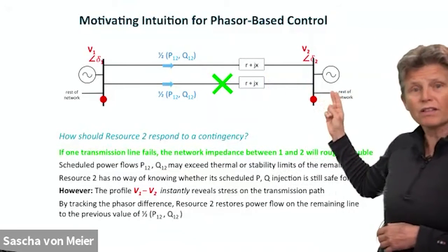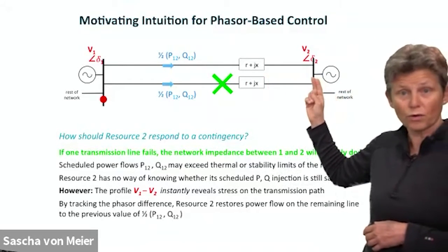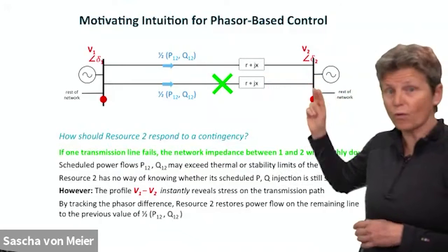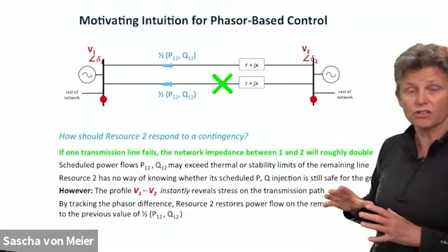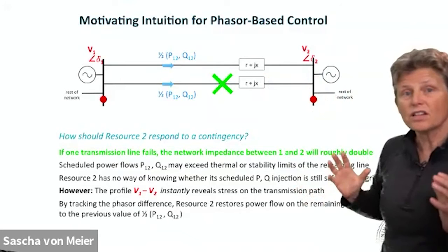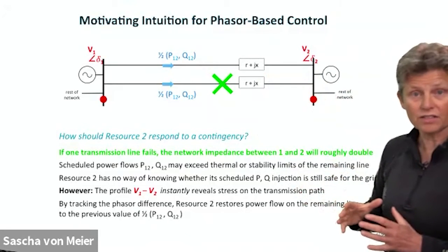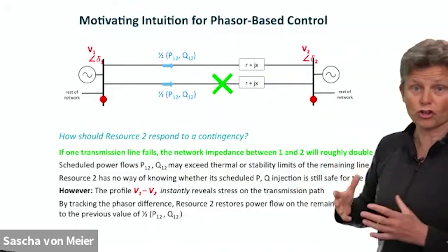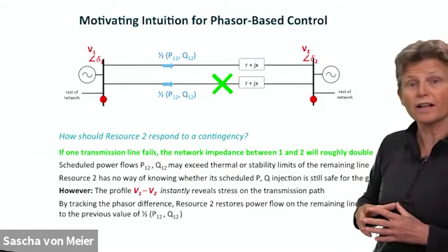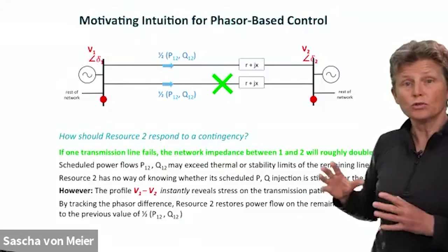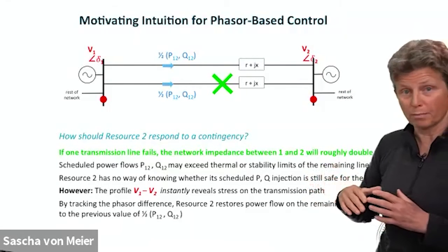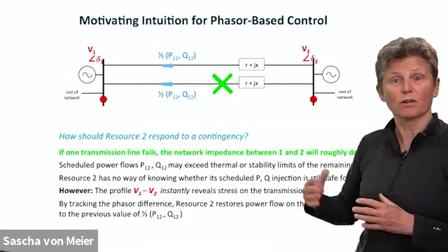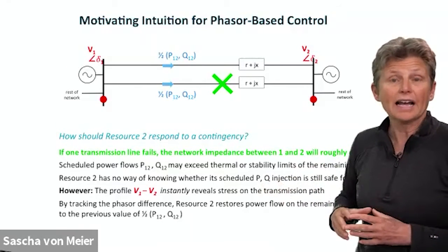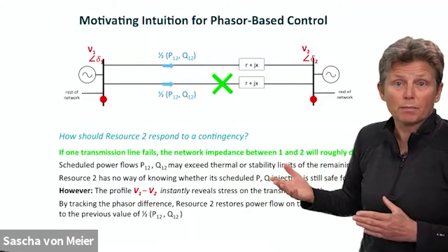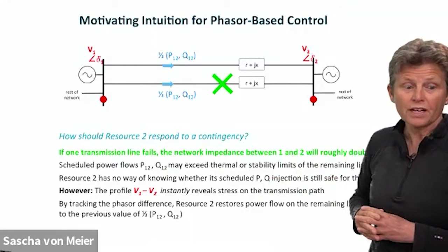By driving this resource back to restore the phasor difference that was there before, regardless of the nature of the contingency, it is acting to stabilize the system. You can show this in a rigorous way, that it will be acting to drive the system away from a possible voltage instability or angle instability, and also away from a possible thermal overload.